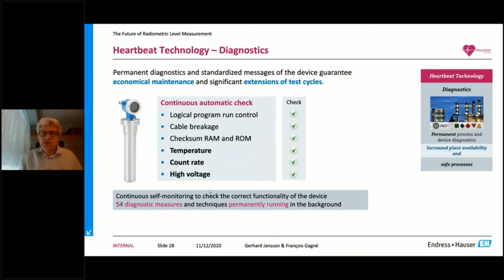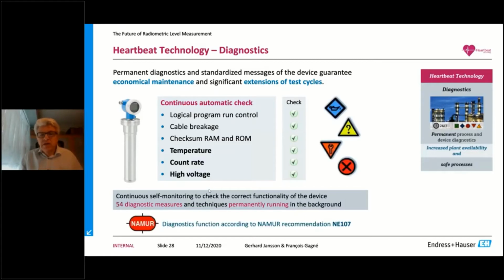We of course want to see a symbol, and I'll get there, which I don't really see here. It's the green check mark. If that is shown, it's good health. Any of these other symbols showing up, then it requires some kind of activity. If it's not a failure, out of specification, maintenance required, it will come up as one of those symbols, plus also a diagnostic code and a little bit of help text telling you what needs to be done. This is of course according to the NAMUR NE 107 standard.